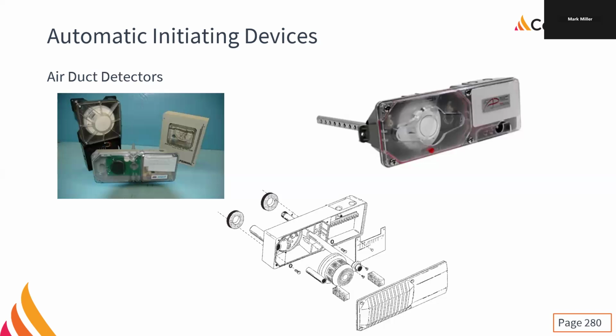And if you need to put a duct smoke detector in your furnace, in the air handling unit in the house, because you have two units, you split the house into a duplex, so we have to keep the smoke from traveling from one to the other. If it activates, it shuts down the furnace. We can do that all with the one unit. It's pretty cool what the stuff can do.